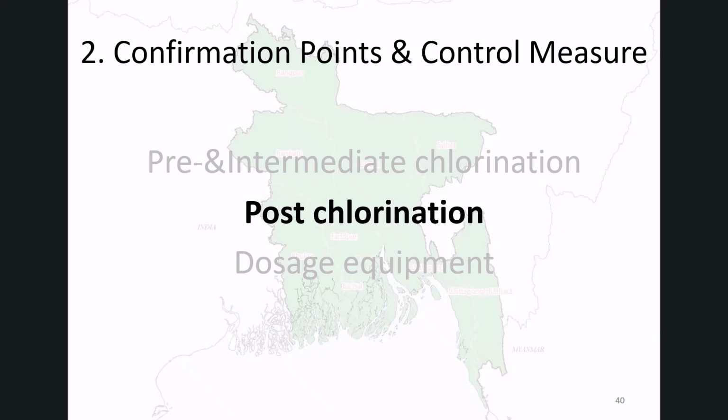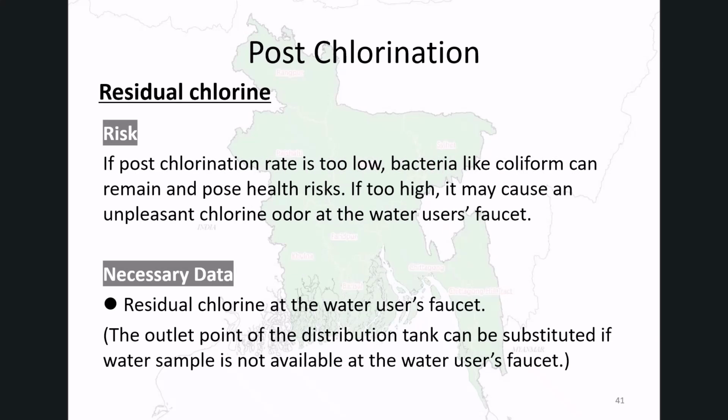Next, post-chlorination. After sedimentation and final chlorination, residual chlorine must be carefully controlled. If the post-chlorination rate is too low, bacteria can remain in the water and create serious health risks. If the rate is too high, users may notice an unpleasant chlorine odor at the tap.